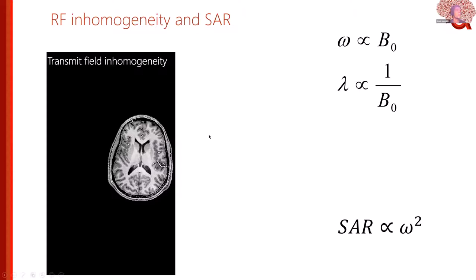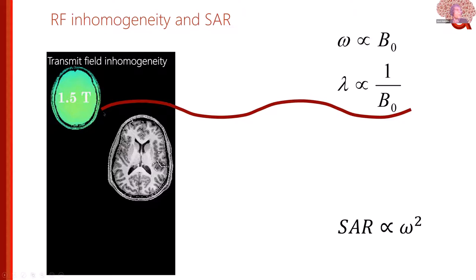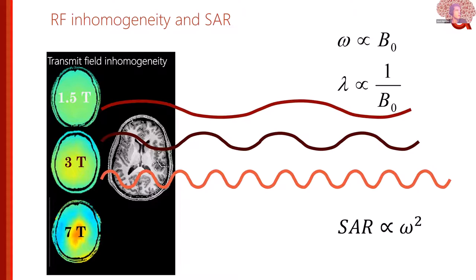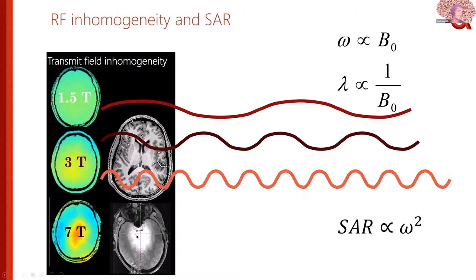One of the biggest penalties of high field, especially relevant for segmentation, is that higher frequencies require shorter wavelengths. At 1.5 Tesla the wavelength is much larger than the brain, so you can illuminate the brain homogeneously. At 3T things get less homogeneous, and at 7T it gets quite problematic. My first images at 7T showed that the thalamic region tends to look brightest because that is where you have the highest SNR or the best excitation.